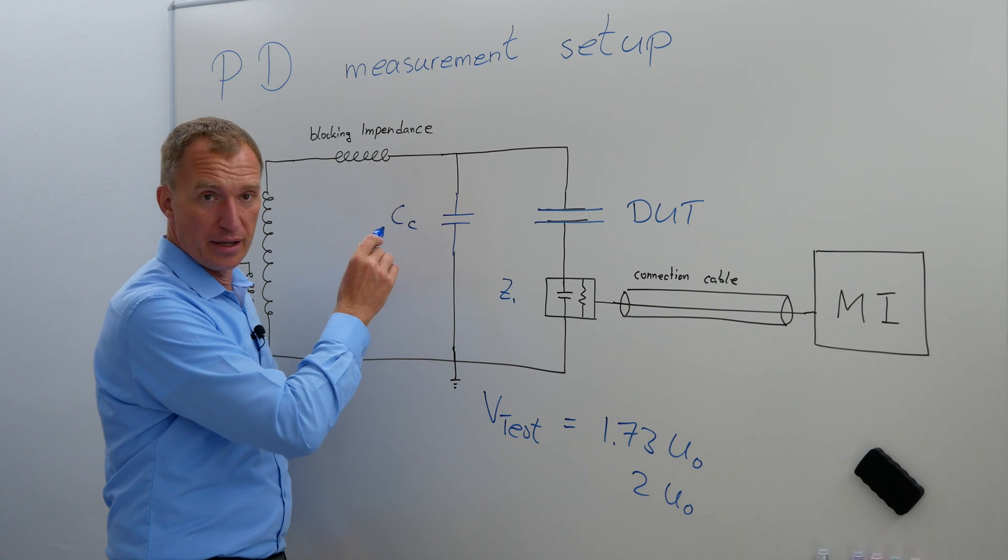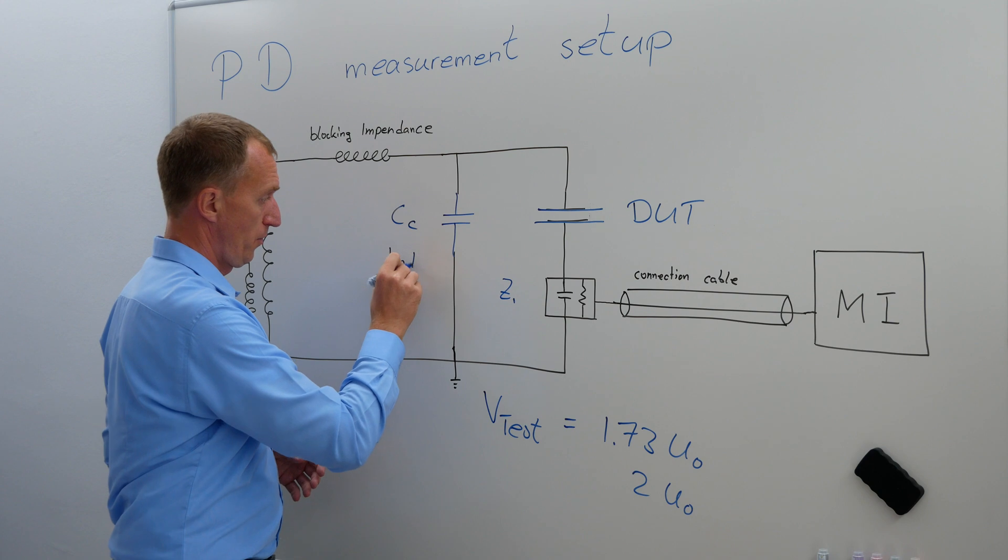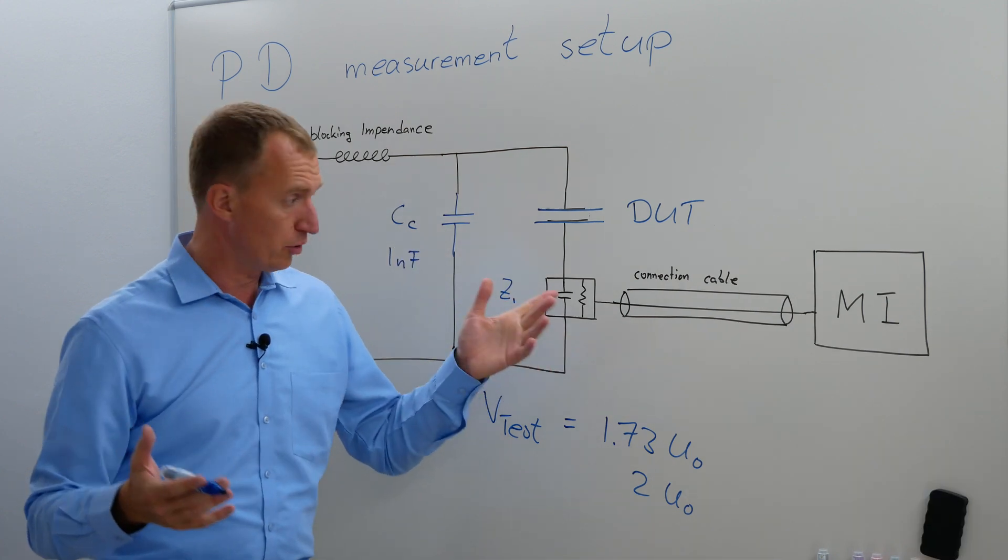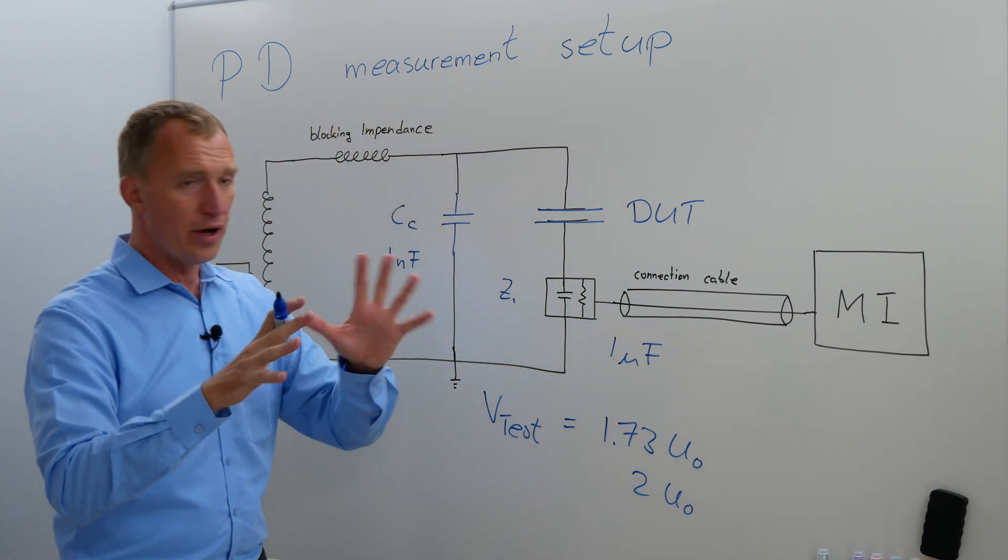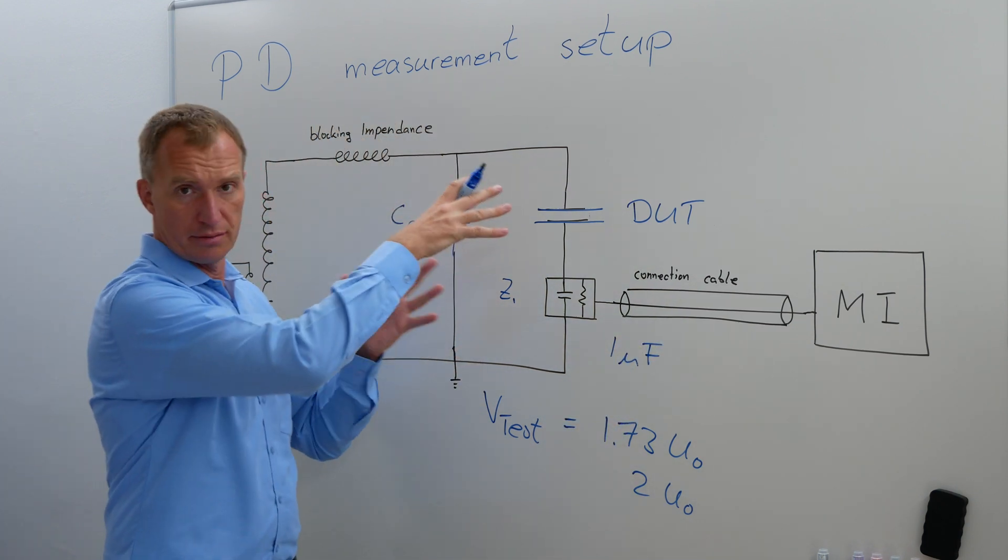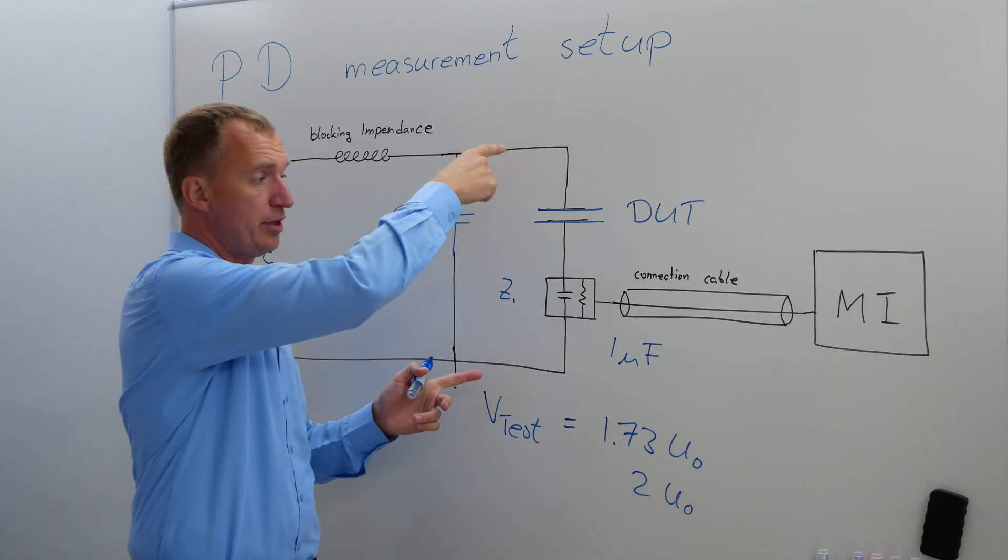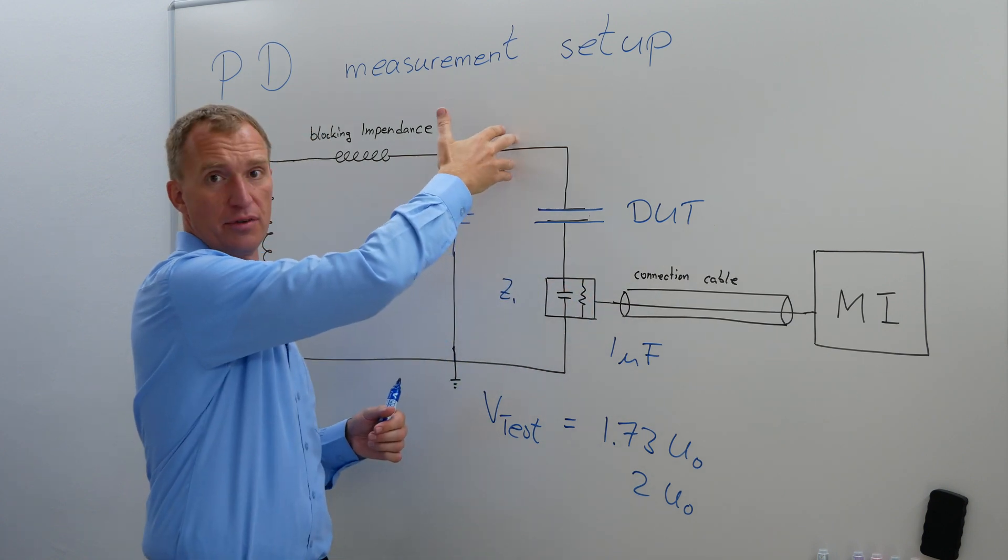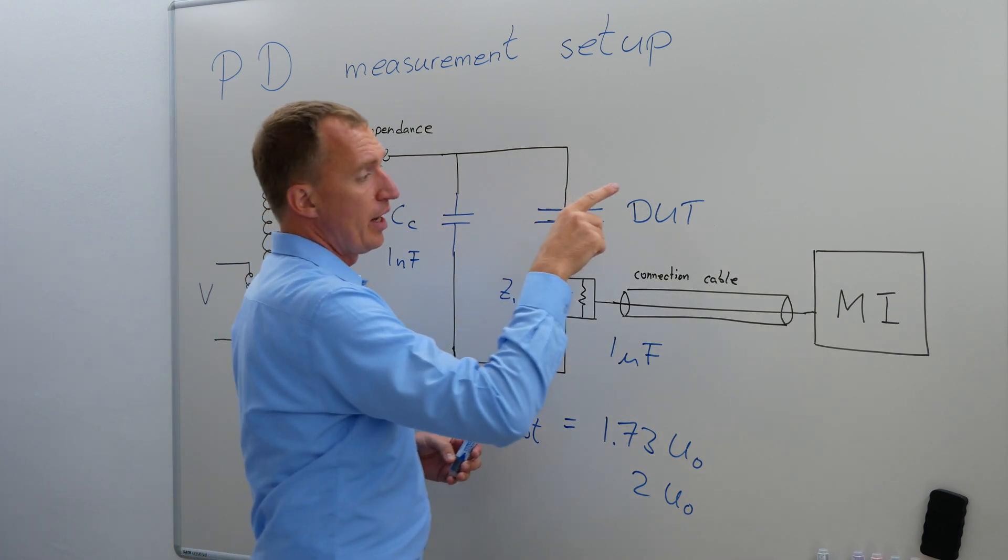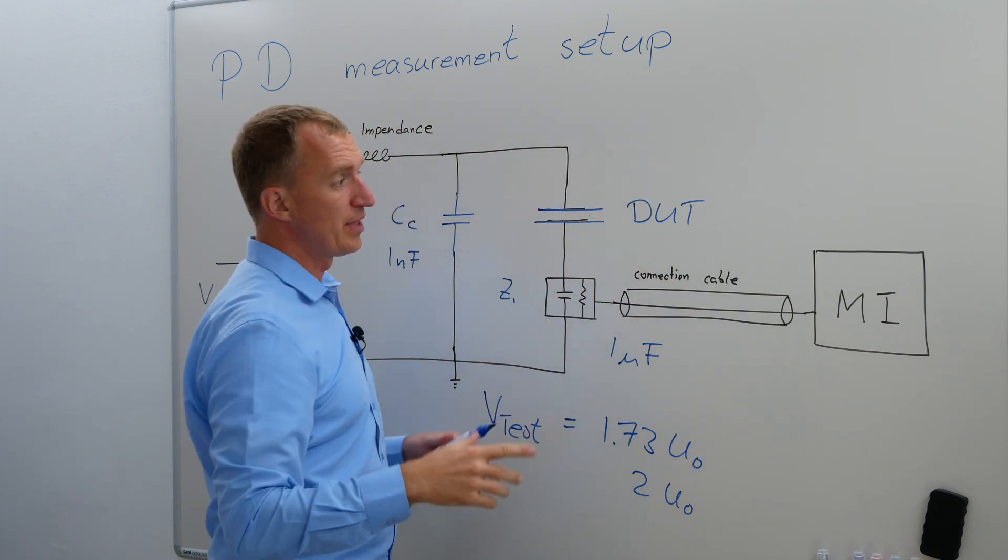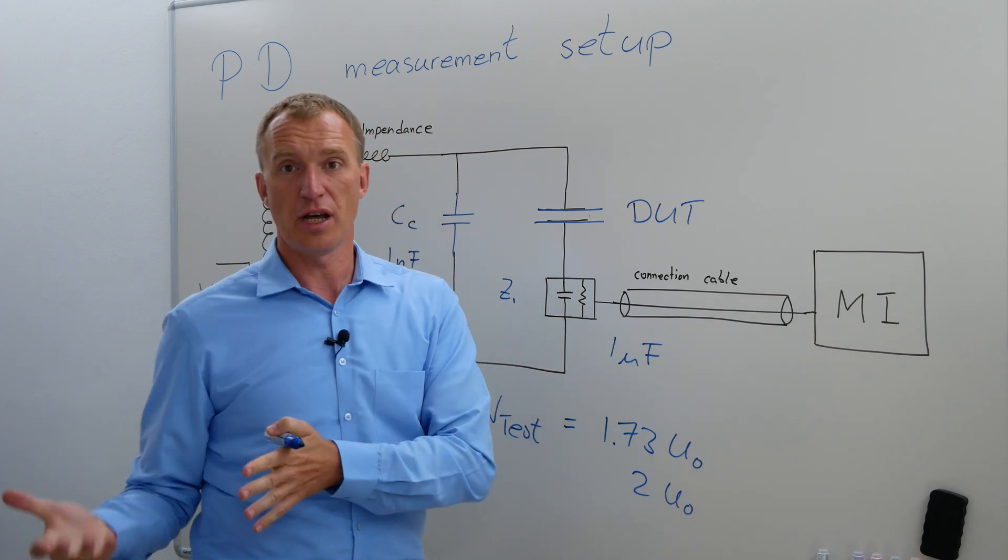If you have a known coupling capacitor, for example one nanofarad, and if your measurement impedance or quadripole has one microfarad, very roughly you had a divider which was a thousand to one, meaning you have one kV here, you have about one volt here. You have 100 kV here, you have 100 volts over there.